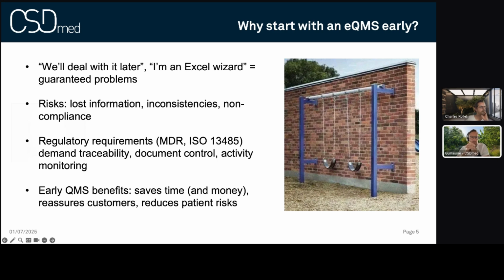QMS is a requirement from MDR. So let me read you Article 10.9. It says, manufacturers of devices other than investigational devices, it's always difficult, shall establish, document, implement, maintain, keep up to date, and continually improve a quality management system that shall ensure compliance with this regulation in the most effective manner and in a manner that is proportionate to the risk class and the type of device.